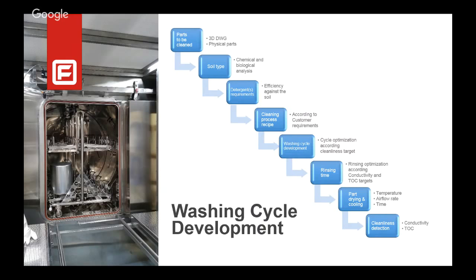To check the cleanliness, we use an optical system: riboflavin spray that is dried on the surface to be cleaned, and then with the Wood's lamp we detect the spots of riboflavin that were not removed by the process. With this system we are able to define the rinsing time that is necessary for this kind of cleaning cycle, and then afterwards we have to size and define the drying and the cooling.